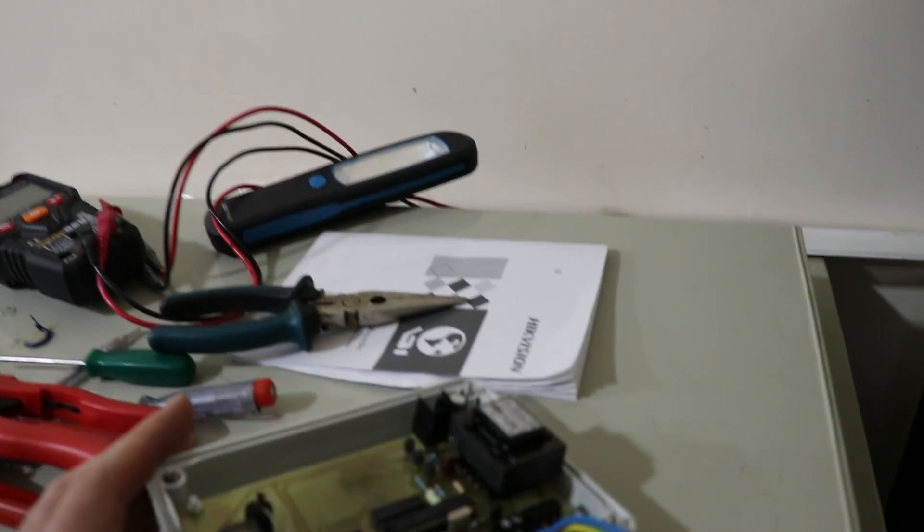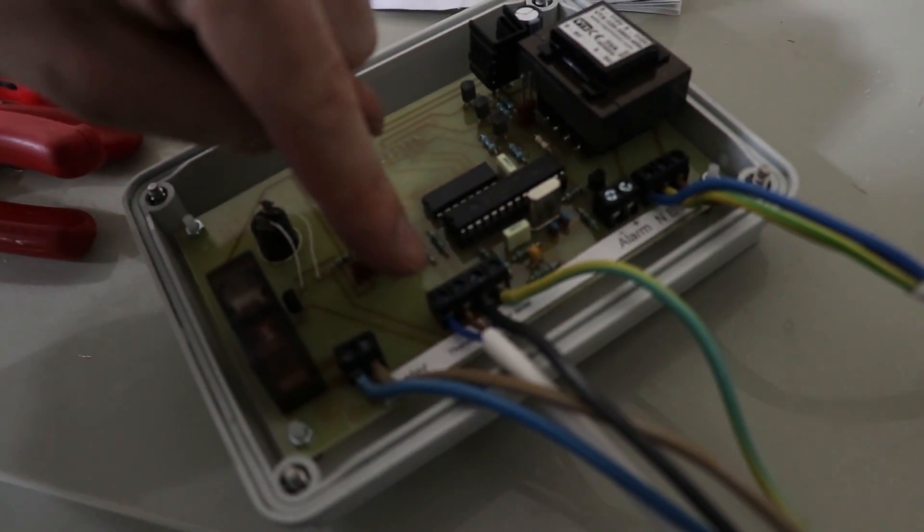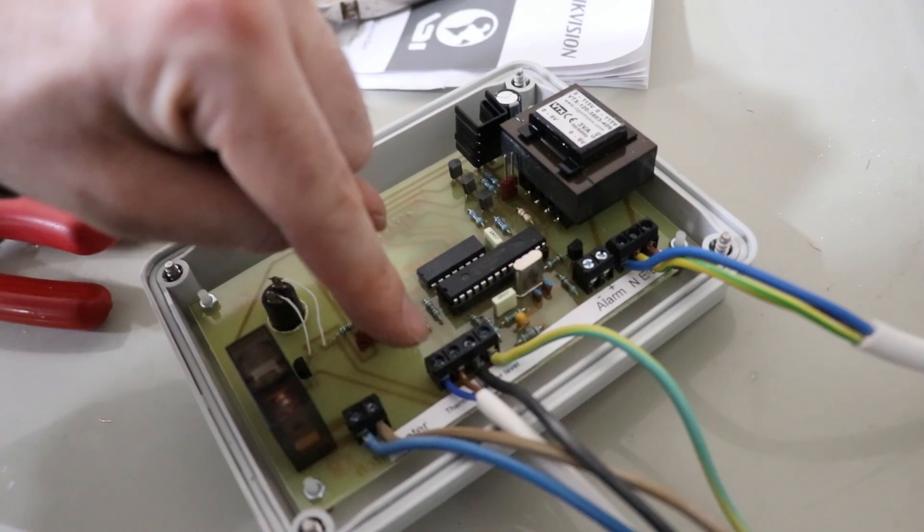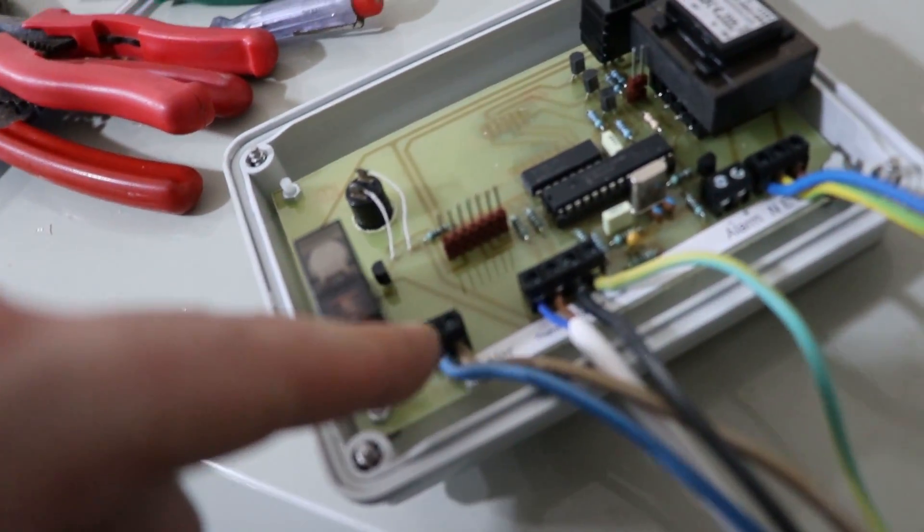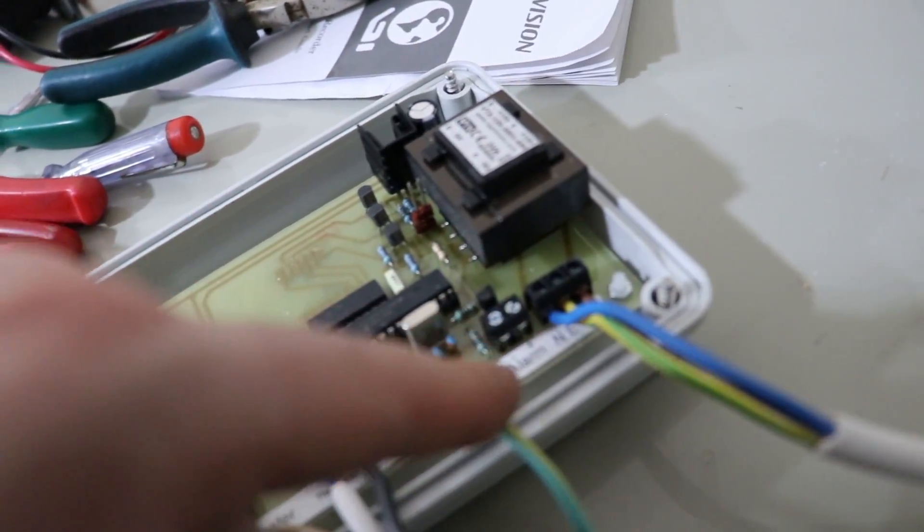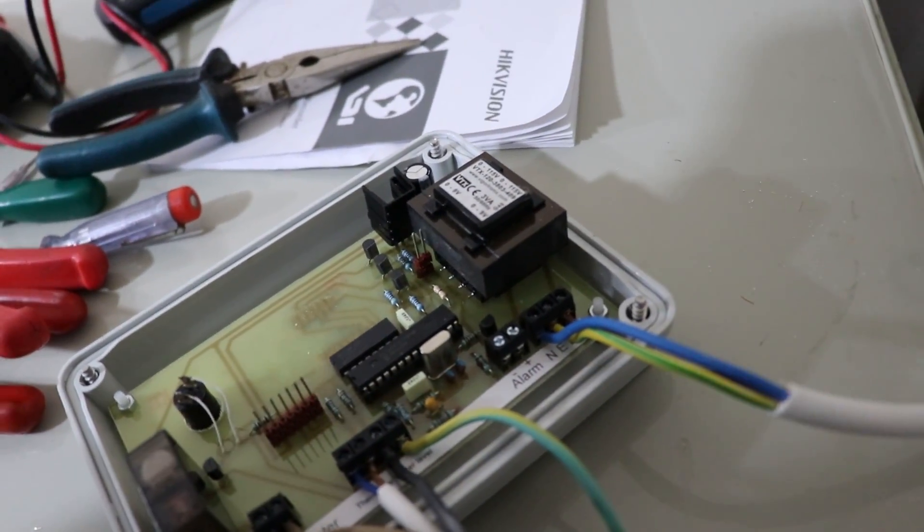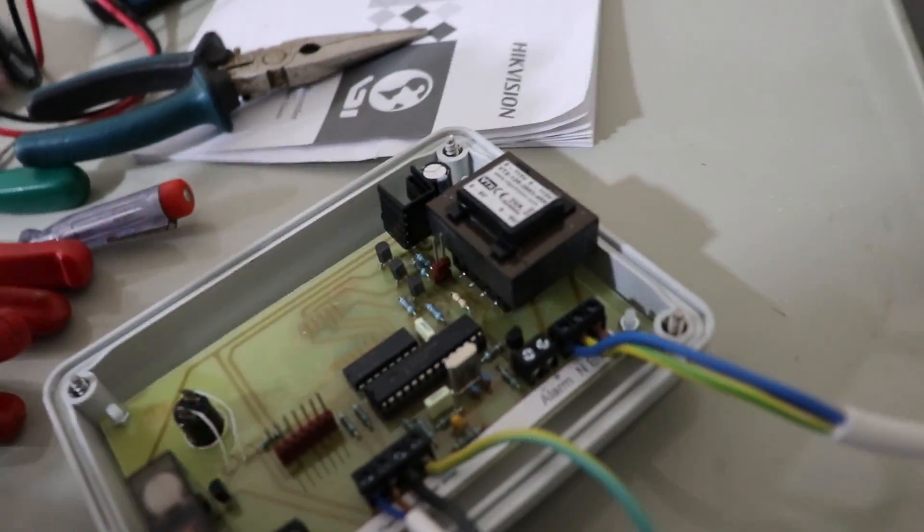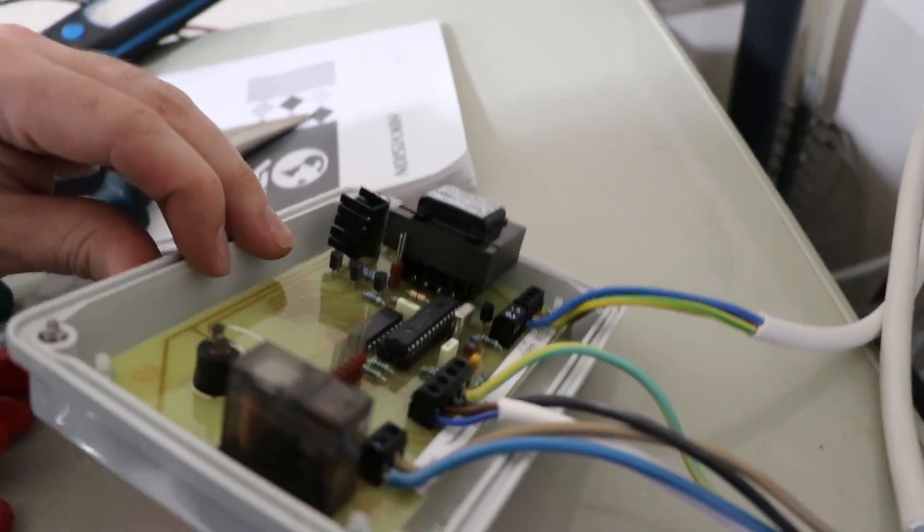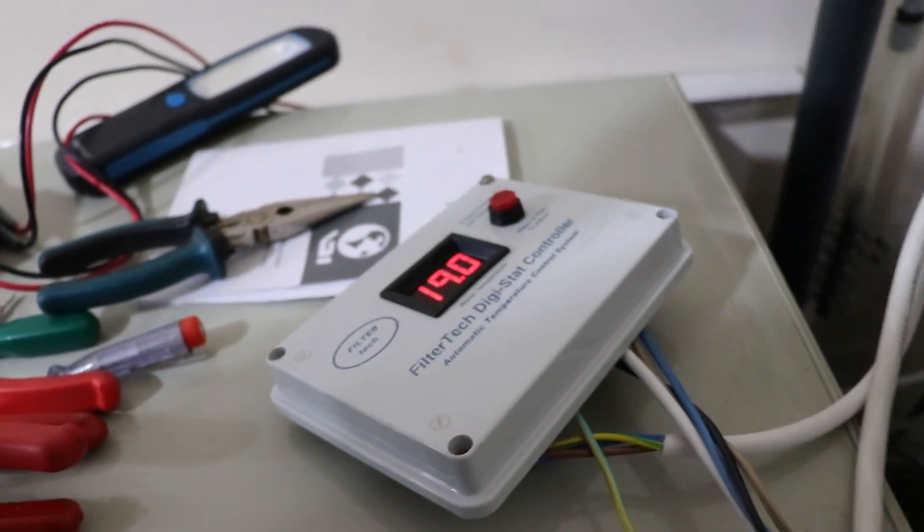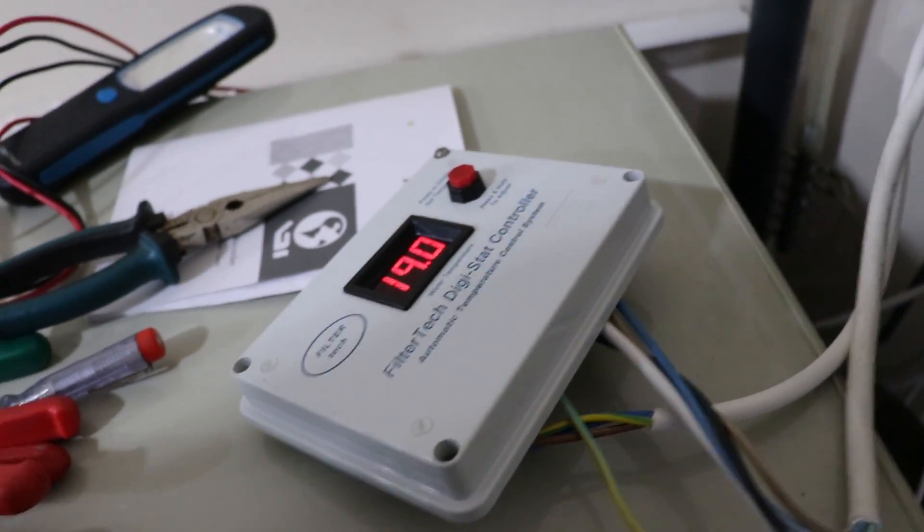The flow switch connects into here, right here, these two pins here. That's your flow switch. These two are your thermostat, your temperature probe thing. That's the word. These two are your heater. And that's your mains. There's actually an alarm output on it. I'm not actually quite sure what it does. I've tried putting voltage across it to see what voltage comes out of it. I didn't really get anything out. So I don't know under what circumstances it would actually start alarming. But there we go.